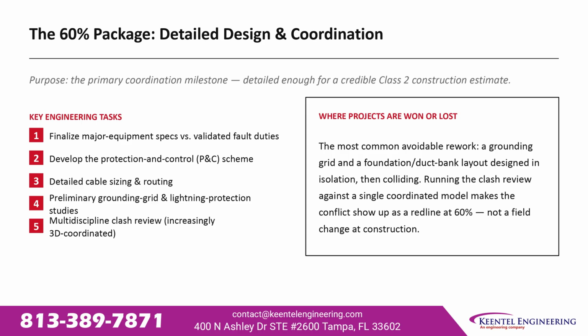The most common avoidable rework is a grounding grid and a foundation or duct bank layout designed in isolation, then colliding in the field. Running the clash review at 60% makes that conflict a red line on a drawing, not a field change order during construction.